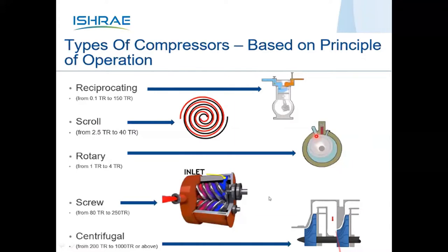The screw compressor technology has reduced power consumption drastically. Although it is a 20-year-old technology globally, it has been seen in India for the past five years. Gas is compressed between two screw lobes — one male and one female. We can increase or decrease the RPM of the screw for a more efficient system. Screw technology is also used for minus applications because it can cater to heavy pressure differentials.